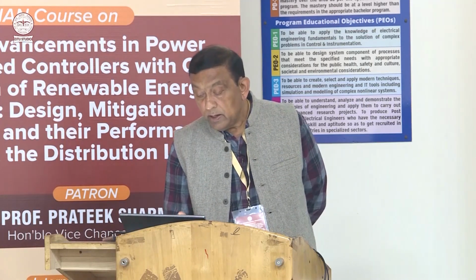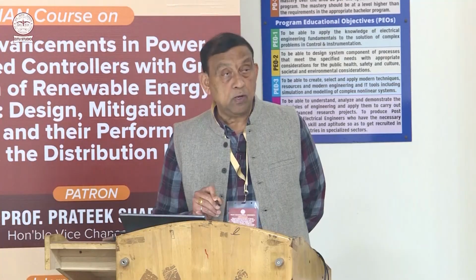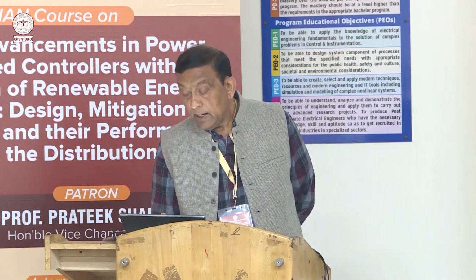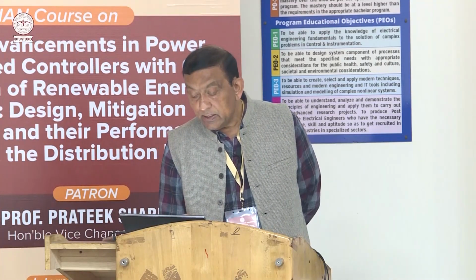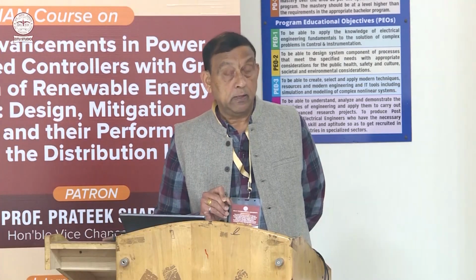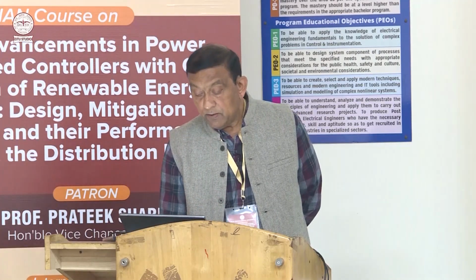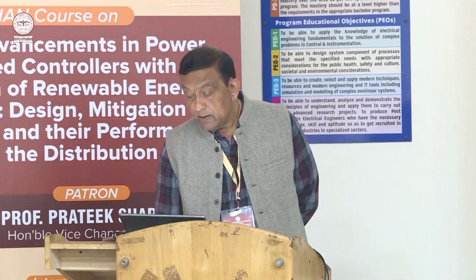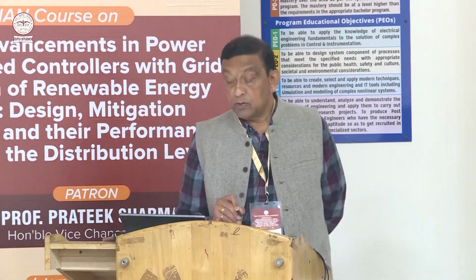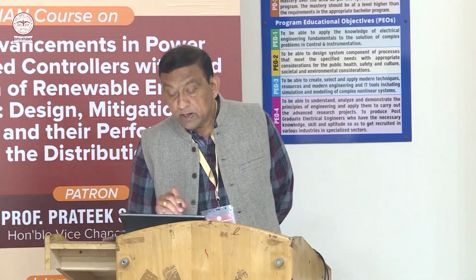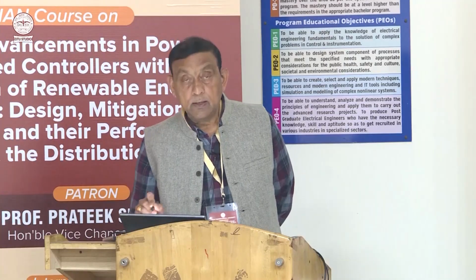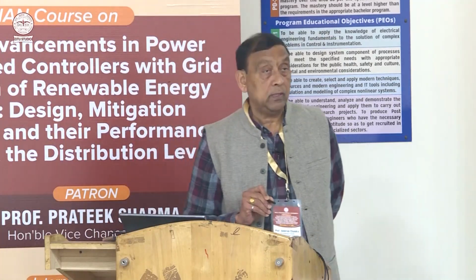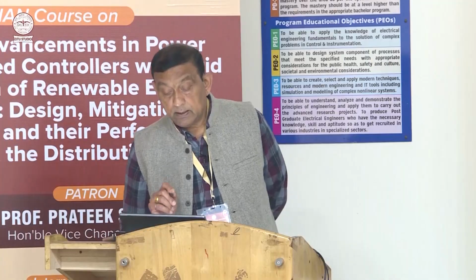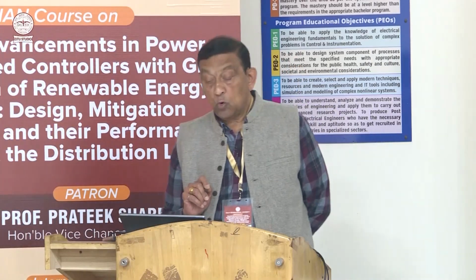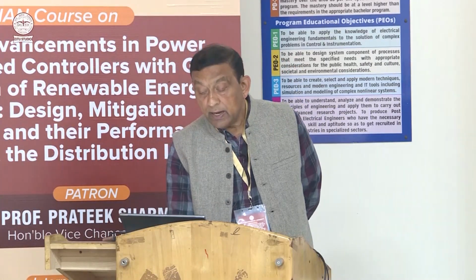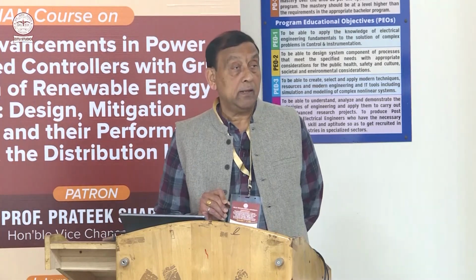According to the Indian Electricity Grid Code, enforced by the Central Electricity Regulatory Commission, the permissible frequency band on the national grid, because you have 50 Hz, is 49.9 Hz to 50.05 Hz. So this is the Indian Electricity Grid Code. For isolated networks, it is not defined.